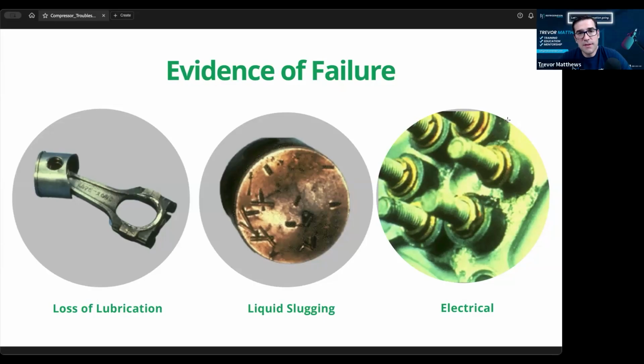And I think that's the big thing, understanding the different telltale signs, because I've opened up so many compressors, and just taking off the head will tell you probably 80% to 90% of the story. Sometimes you've got to dive in deeper, and it's really hard to figure out problems on those tricky ones. But for a slug, a lot of times you can pull that head off and you can tell it took a slug. So it's either oil or liquid. Which one was it? How did it actually happen? You know what I mean? And I think diving in to tell the story, because I know for sure you could get a compressor back.